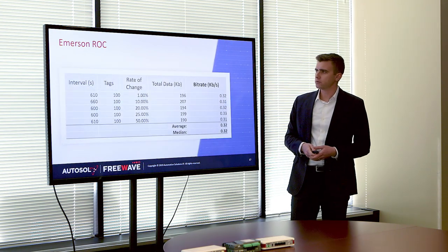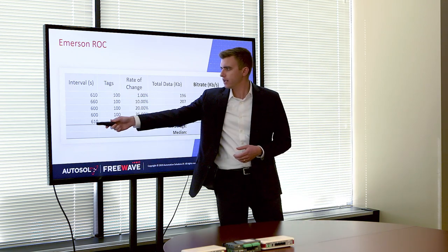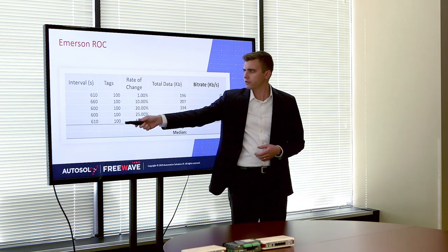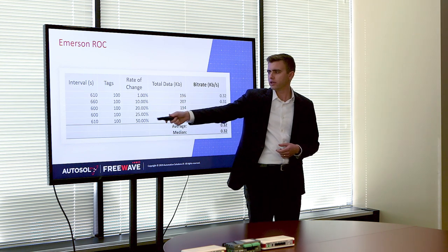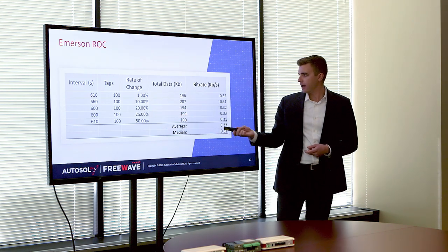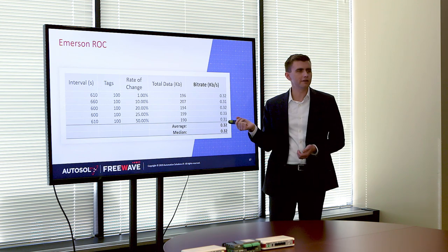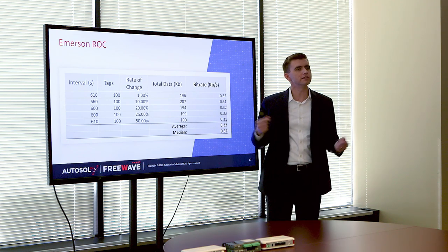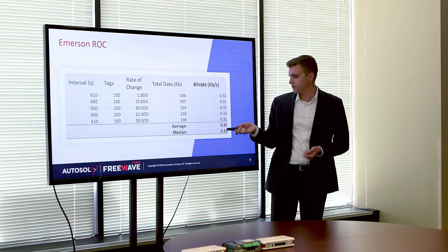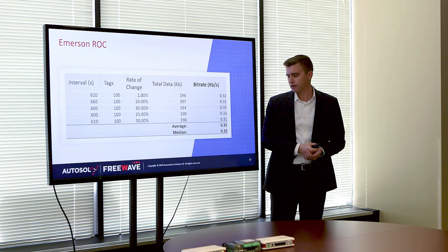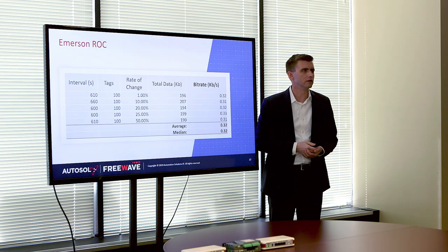Here are the results from the ROC test. We have our time interval, 10 minutes, 100 tags, rate of change 1%, 10, 20, 25, and 50. The bit rate is significantly smaller than Modbus because we have one-tenth of the number of tags. But again the average and median are the same — 0.32 kilobits per second used to bring 100 ROC tags over, no matter what the rate of change.